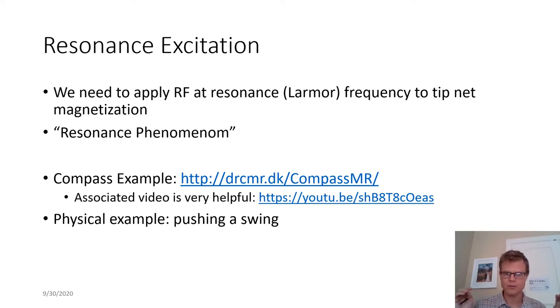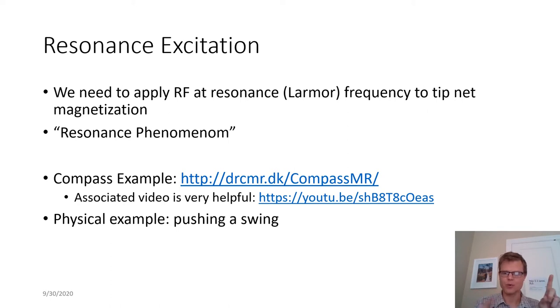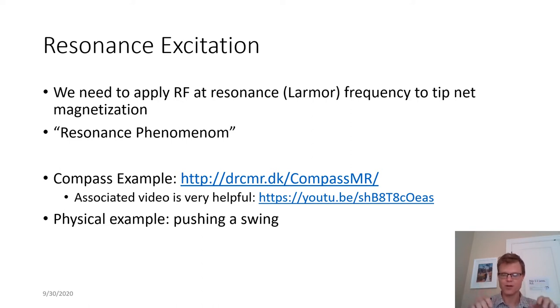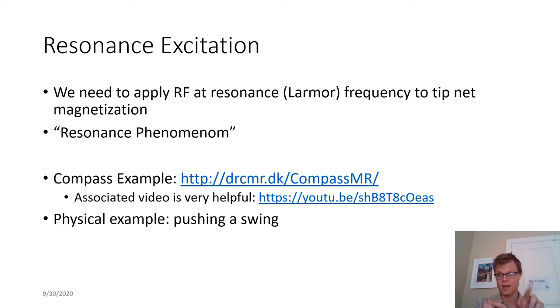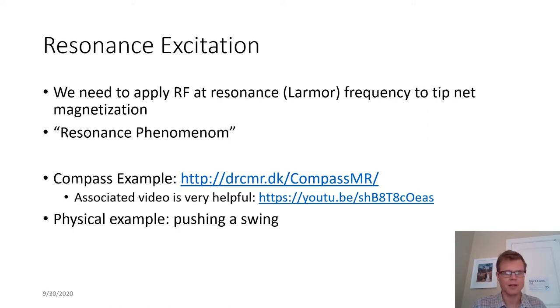In the swing example, equilibrium is the lowest energy state — the swing hanging down. In MRI, it's the net magnetization pointing along the z-axis. The resonance is that in the swing example you pump your legs back and forth at the right frequency, swinging higher and higher. In MRI, we apply our perpendicular RF field at the right frequency, and it gradually tips the net magnetization further and further away from the z-axis, as seen in that animation. Without this resonance condition, we cannot get excitation of our net magnetization — we cannot get signal.